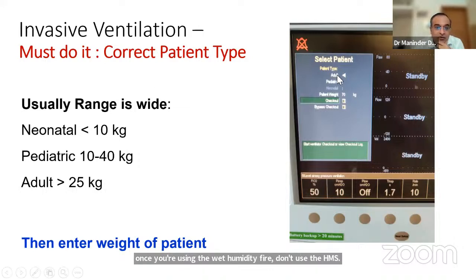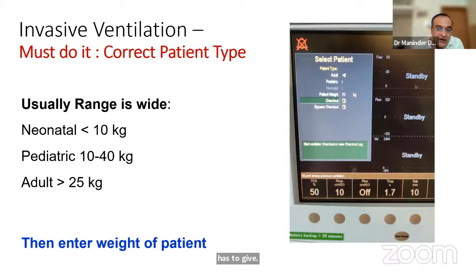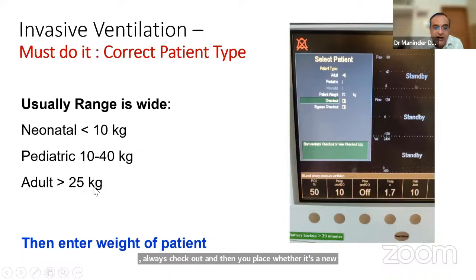Again, once you start your ventilator, you should know what patient you are applying it to. Because once you select a neonatal, pediatric, or adult ventilator, the machine has inbuilt parameters - it knows which circuit is going to be attached, and what bias flow the machine has to give. So it's very important, whenever you start a ventilator, to always check and set whether it's a neonatal, pediatric, or adult patient.